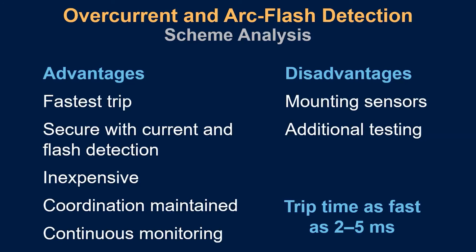Because it's completely selective, you can leave it on all the time. So that does away with human performance errors. Because it's selective, we don't overtrip even when personnel are present, but also because it's selective, I can leave it on all the time.